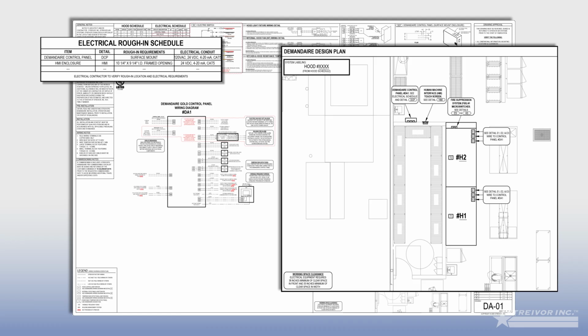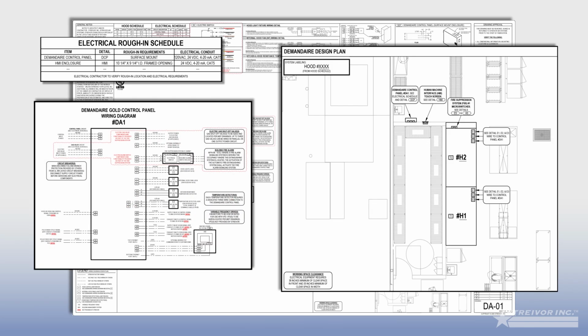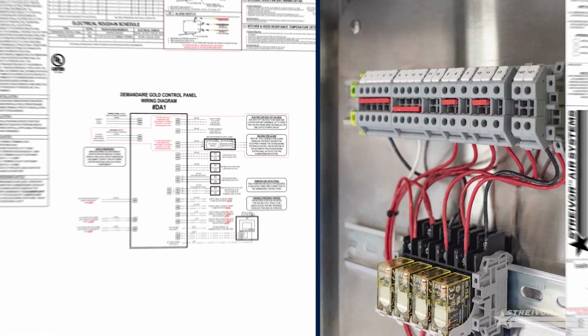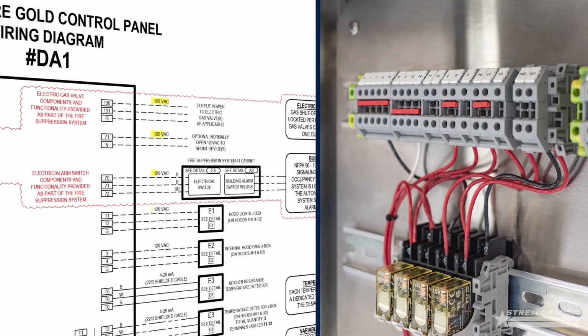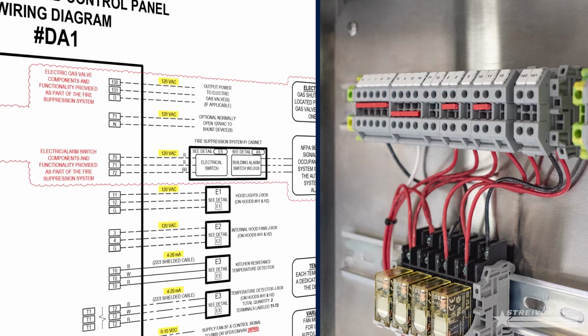Now that you have an overview of the system, proceed to the control panel's wiring diagram for details on inputs and outputs that the accessory should be connected to. Take a moment to identify the connections and the terminal blocks associated with each accessory. For additional clarity, each connection is labeled with the required electrical voltage on the DemandAire drawing.